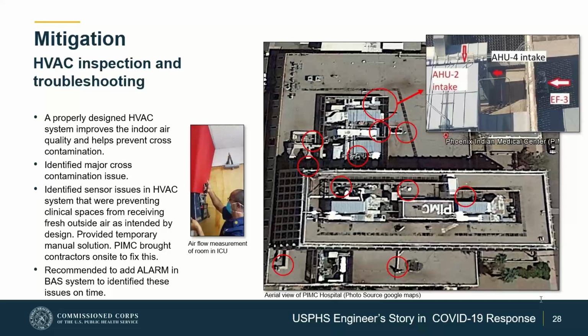Some major issues we found were dampers that were stuck or had a bad sensor, which meant the HVAC systems or air handling units were unable to bring in the proper amount of outside air required by code. These are minor issues in themselves, but when you do not look into this stuff for a long time, dust and other natural causes can make a damper not function as it was designed.